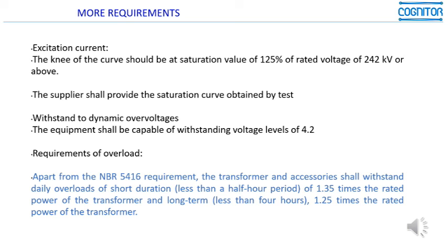But in the peak hours, which usually is a period of 4 hours at the end of the day and the beginning of the night, the transformer is overloaded to values like 110%, 120%, 130%, and these occur with certain durations during every day. And here is one example of the requirements included in the specification of these transformers for a 230 kV.